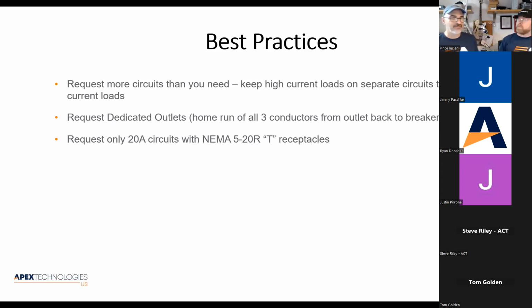What will happen if you did that? Let's say you cut your connector off on your 20 amp load, or you used an adapter to plug it in. All you're doing is screwing yourself, because it may not be on day one, but sometime that 20 amp load is going to pull the full 20 amps. It's going to trip that breaker. You're going to get the service call, and all you're going to do is bring it over and reset that breaker until the next time you trip that breaker. So you never want to do that.